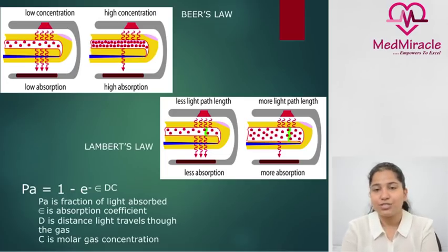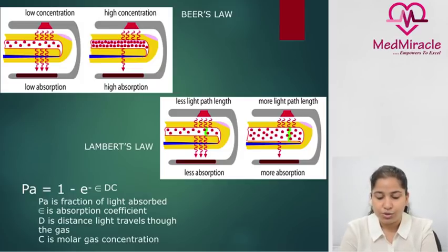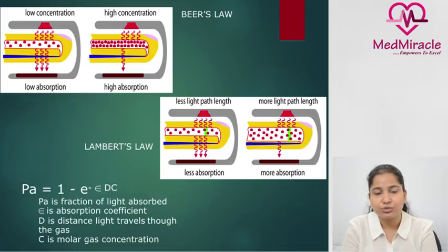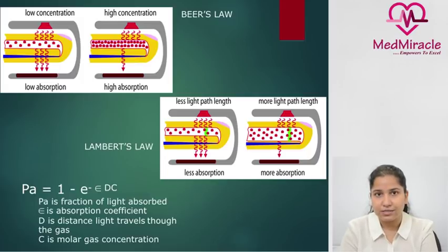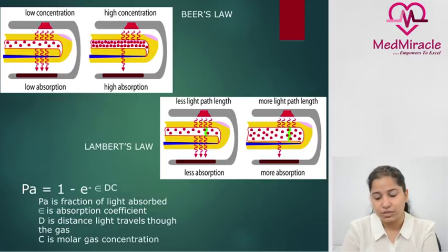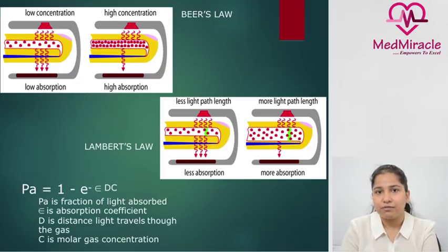Pulse oximetry is based on two important laws: Beer's law and Lambert's law. According to Beer's law, absorption depends on the concentration of the molecule absorbing the light radiation. So as the concentration of hemoglobin and oxyhemoglobin increases, the absorption of that particular wavelength also increases. According to Lambert's law, as the distance traveled by light increases, the amount of absorption also increases.